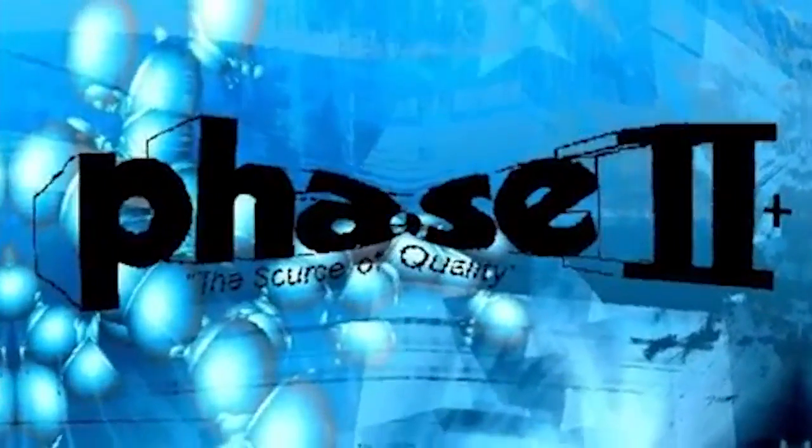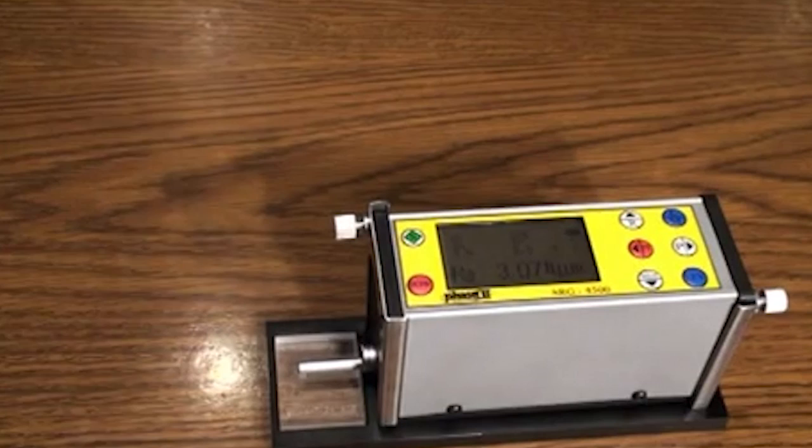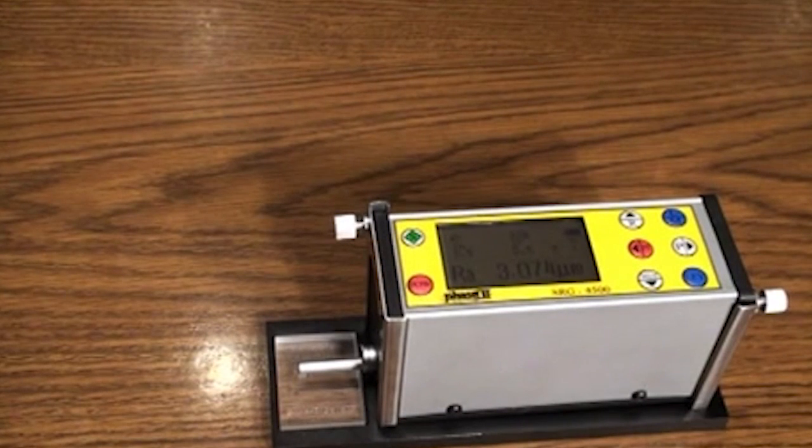This is an instructional video detailing the applications and functions of the Phase 2 SRG-4500 Surface Roughness Tester. The SRG-4500 is an instrument designed to check surface finish with measured values displayed on a digital readout in various surface roughness parameters. Note, the SRG-4500 is an extremely sensitive instrument and should be treated with care to assure measurement accuracy and reliable performance.